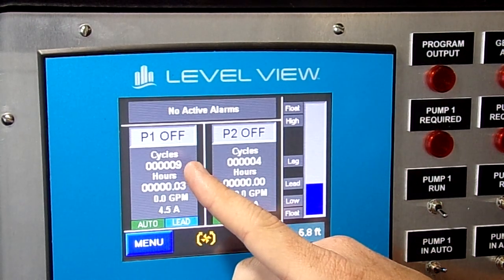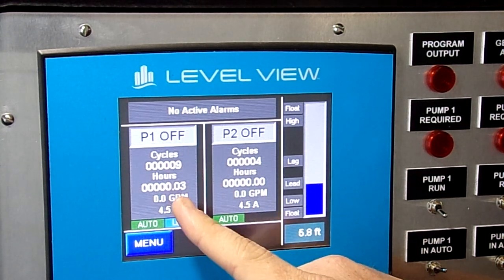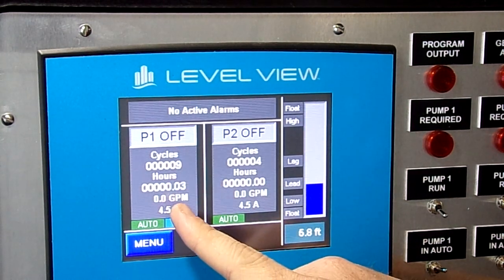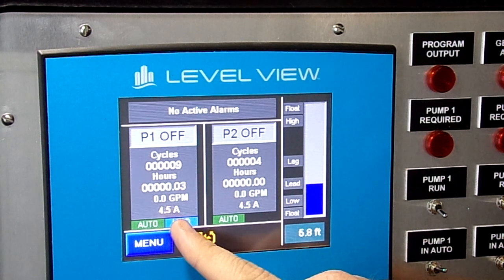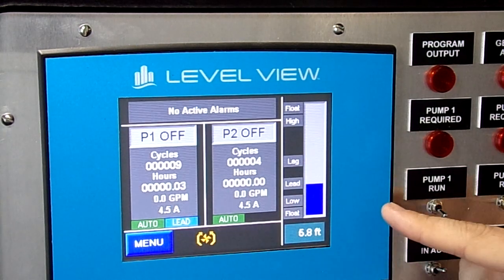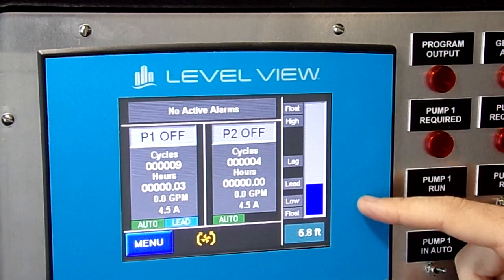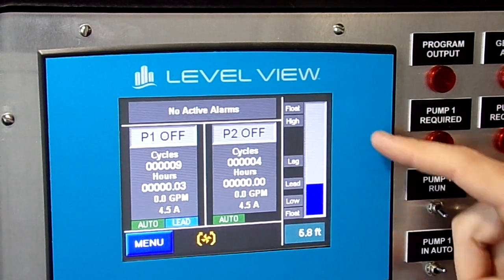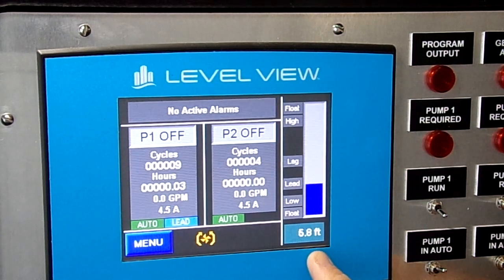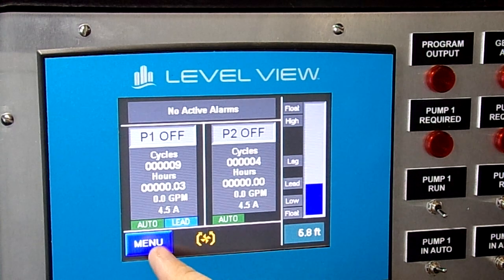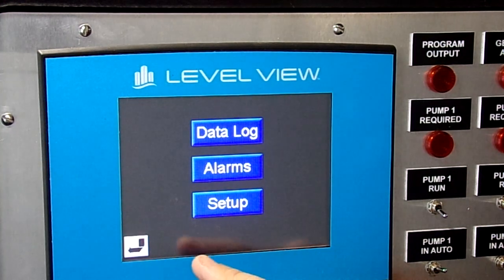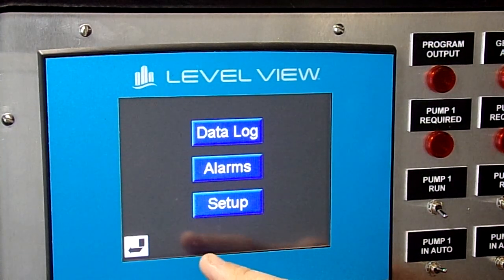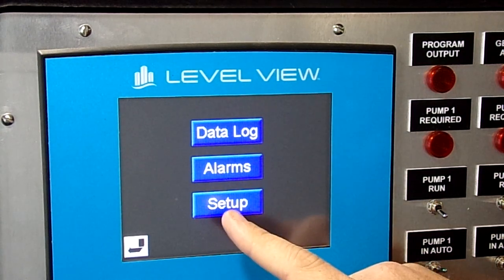On the main menu or the home screen, we can see our cycles, our hours, our gallons per minute, and our amps for each pump. We will also have the level indicator of where our transducer range is, as well as an approximate range of feet with the transducer. If we click on our menu button, it'll bring us to the main screen where we'll have data logging, alarms, and setup.